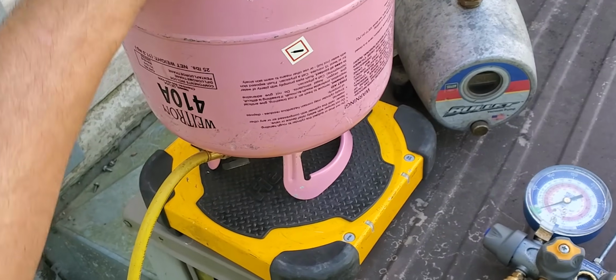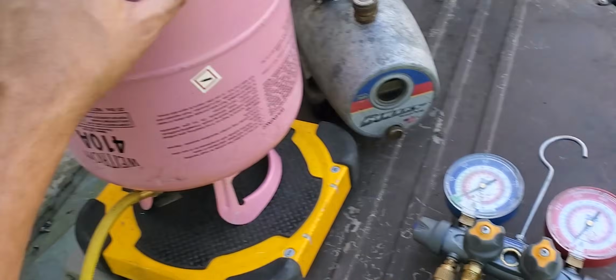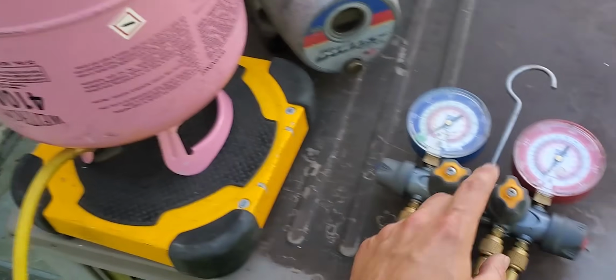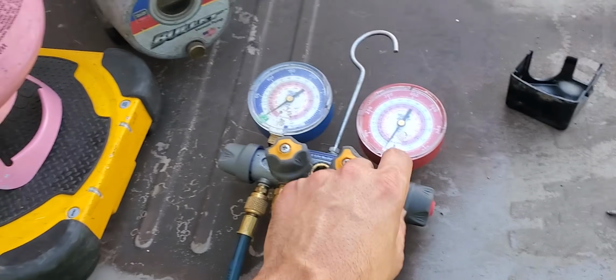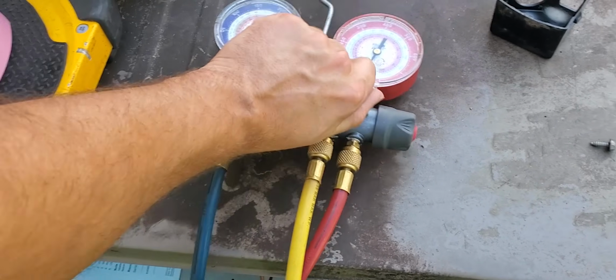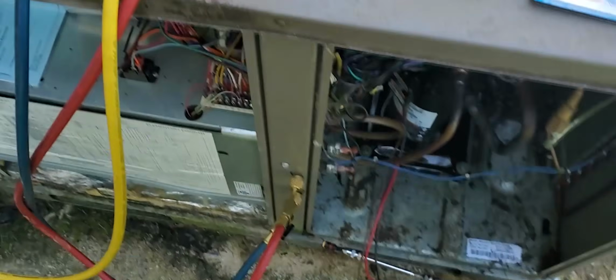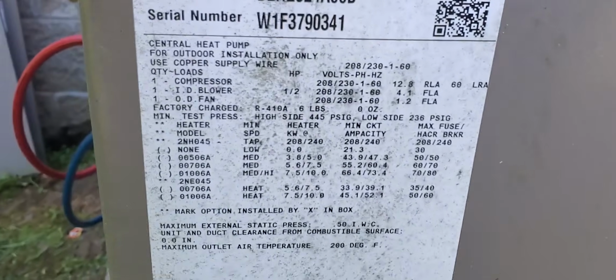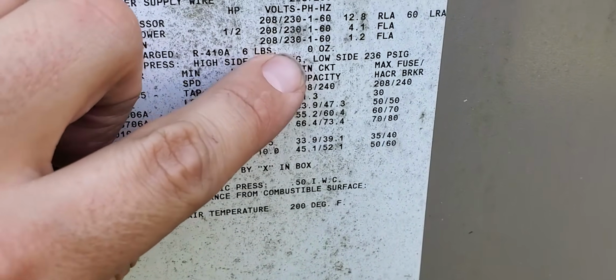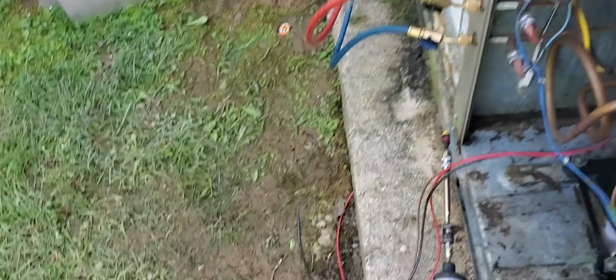Got my scales, Fieldpiece wireless scales. I'm going to charge the system up. Always charge upside down so you have liquid, and charge through your high side. Filling up that condenser section there. Also want to do factory charge. So I'm going to put in 6 pounds and 0 ounces. Zero my scale out and then start adding. We're adding through this line here.